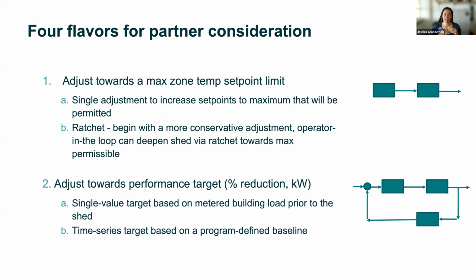You could do that all in one step. Or you could do it with a ratchet-based approach where you go a little bit at a time, maybe not even all the way to the max if you're happy with the response you're getting. That may be an operational policy perspective, or it might just be contingent on the equipment you're interfacing with - you don't get a lot of modulation on package systems the way you do from built-up VAV systems.